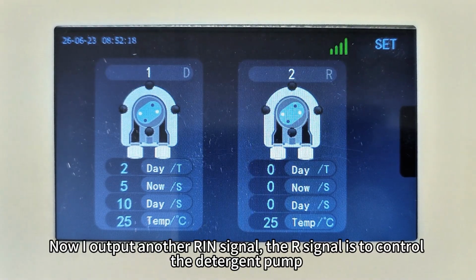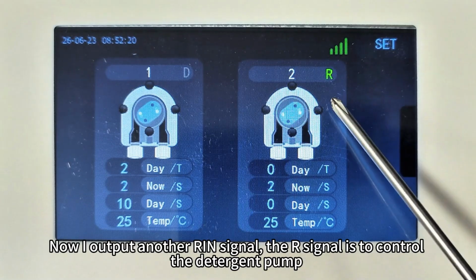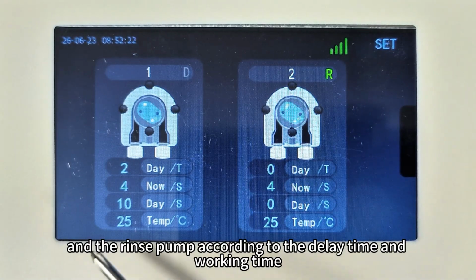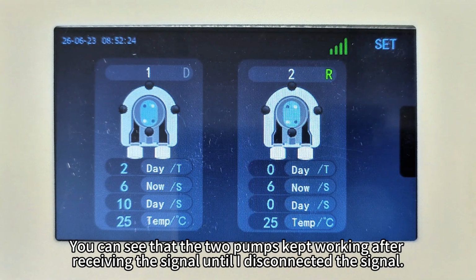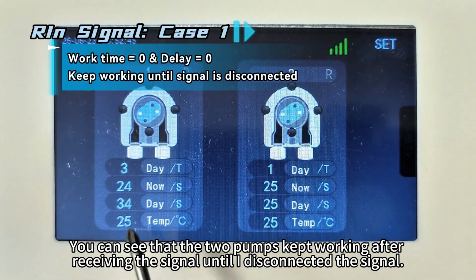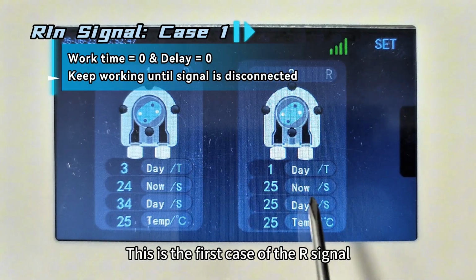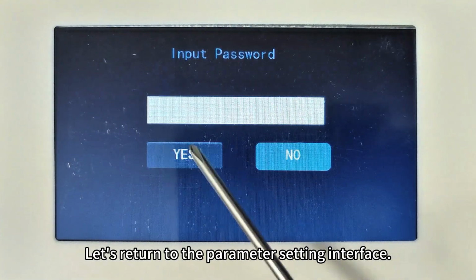Now I output another RIN signal. The RIN signal controls the detergent pump and the rinse pump according to the delay time and working time. You can see that the two pumps kept working after receiving the signal until I disconnected the signal. This is the first case of the RIN signal. Let's return to the parameter setting interface.